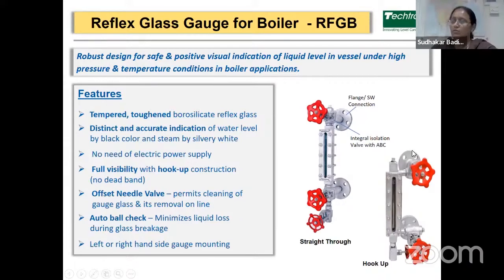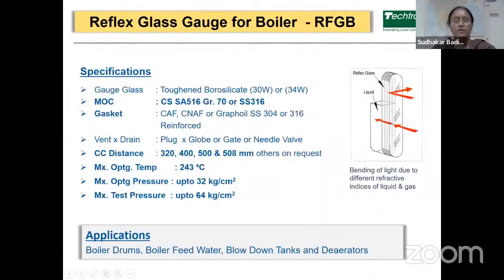Then the process connections are available with flange connection and screwed connection. It has two types of gauge mounting, that is left-oriented and right-oriented gauge mounting, to suit your applications or the mounting position. The specifications are, you can go through it. Material is available as CS SA516 grade 70 or SS316. The gaskets can be CAF, CNAF, Graphoil, SS304, 316.